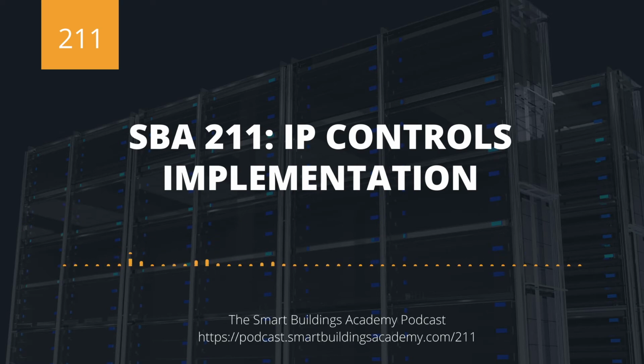It is perceived as less secure because you have multiple MAC addresses. Remember that an IP device is going to have a MAC address for its network interface card. That's the physical address. It's not to be confused with an 8-bit MAC address that you set via a dip switch on a field controller. This is an Ethernet MAC address, and it gives a unique address to each network interface card and ultimately each device.